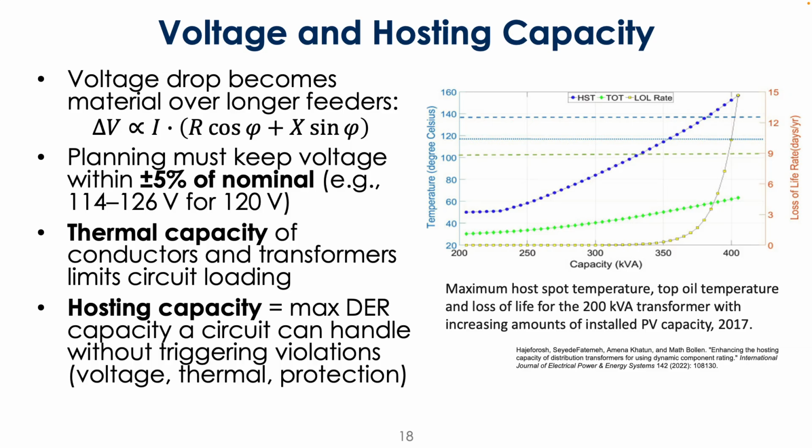Hosting capacity is the maximum amount of capacity a circuit can handle without triggering some kind of voltage protection or thermal limit. Sometimes the thermal capacity itself might be set at a lower level than the hosting capacity.